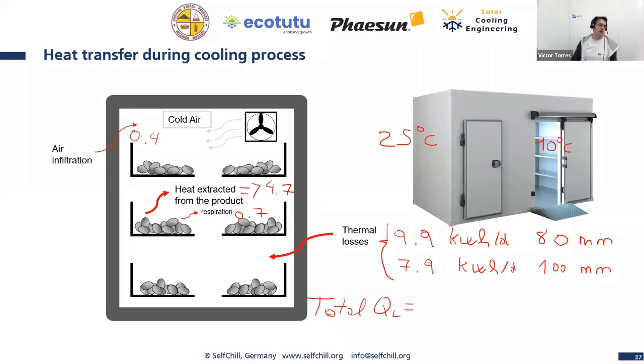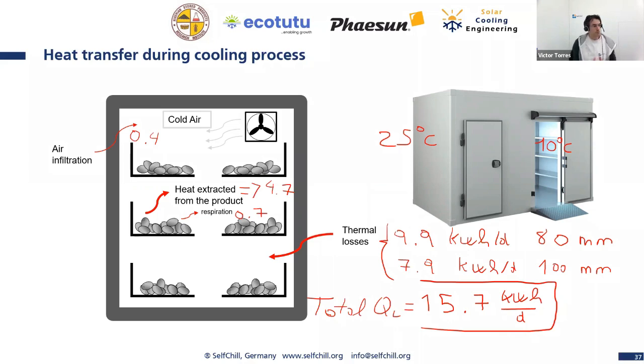So I have here 15.7 kilowatt hour per day. Very nice, this is a very important number. This is very important that we need to know before we continue with the calculation of the thermal storage, the calculation of the PV panels, batteries, and so on. So congratulations, you are able to calculate the thermal load of a cold room.